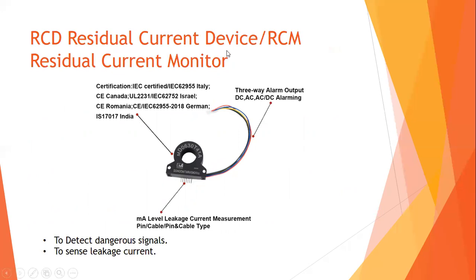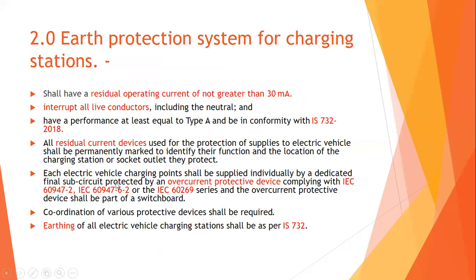A residual current device (RCD) or residual current monitor (RCM) detects leakage current and sends signals to a monitor so precautionary measures can be taken. RCDs are used majorly for safety. Each electric vehicle charging station shall be supplied individually by a dedicated final subcircuit protected by an overcurrent protection device complying with IEC 60947-2, IEC 60947-6-2, or the IEC 60269 series, and the overcurrent protection device shall be part of the switchboard.